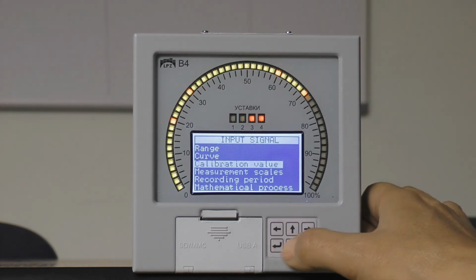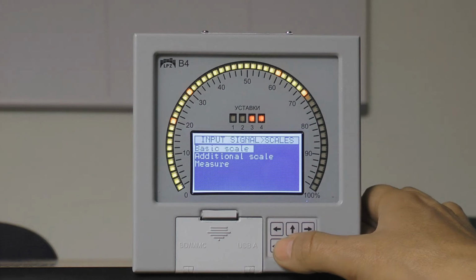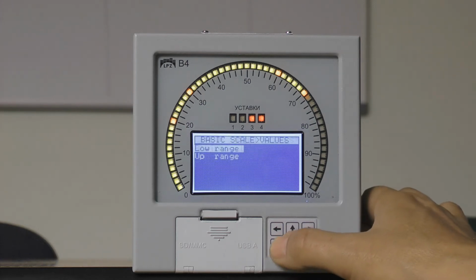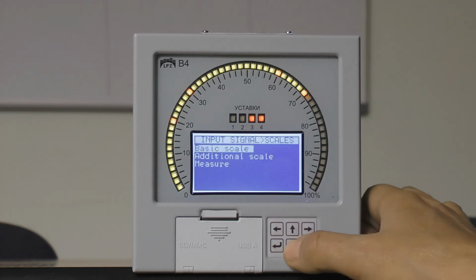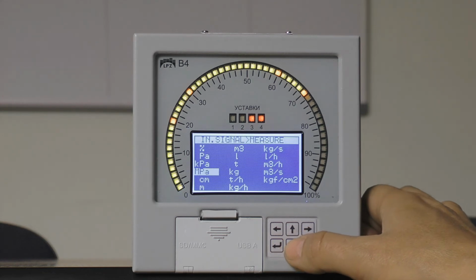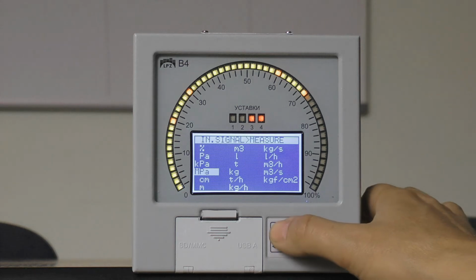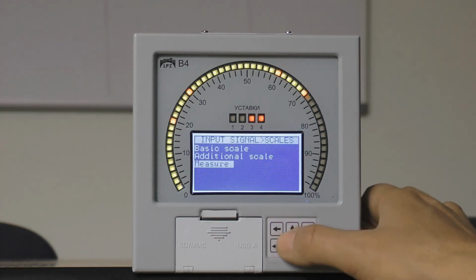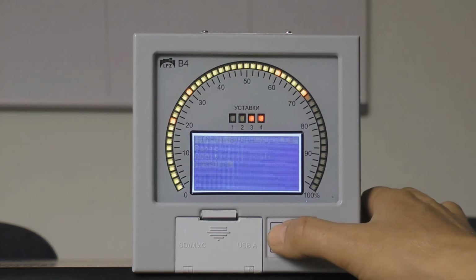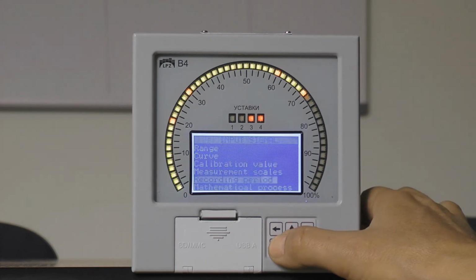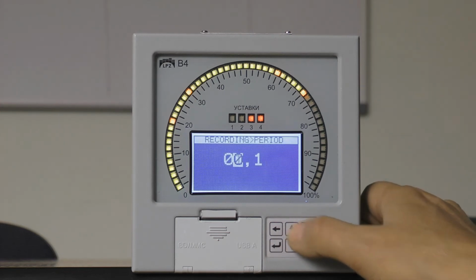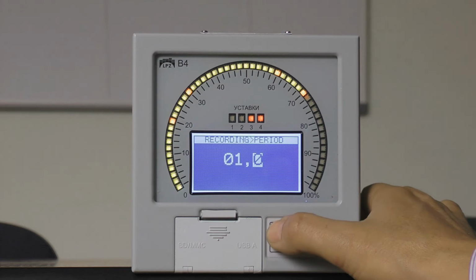This is the measurement scales menu. Here you can adjust basic scale, additional scale, and measure scale, low and up values for each range. We will explain why you need a precise range a bit later. After it, we choose measurement units out of a standard set. You can also change and complement this set if you wish. Now I would like to go back in our menu and show you how to adjust the period of data recording to the SD card, which is from 0.1 second to 99.9 seconds.